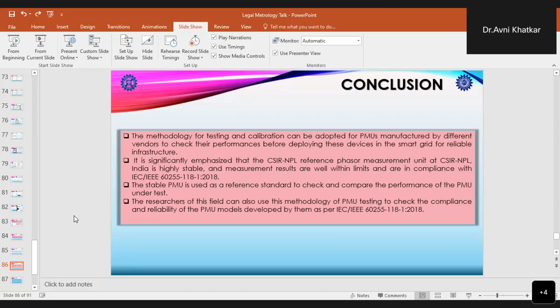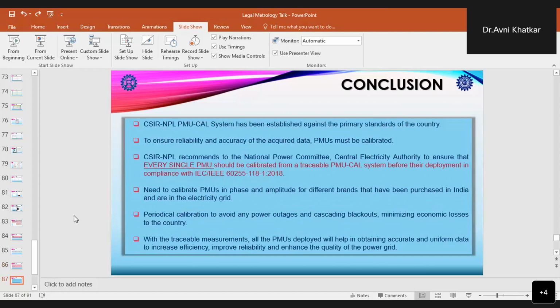And researchers from this field can also use this methodology of PMU testing to check the compliance and reliability of the PMU models developed by them as per the IEEE standard. Also, the CSIR NPL's PMU calibration system is established against the primary standards of the country, and to ensure reliability and accuracy of the acquired data, all the PMUs should be calibrated. CSIR NPL also recommends to the NPC that, to ensure this, every PMU should be calibrated from a traceable PMU calibration system before deployment, in compliance with the IEEE standard.